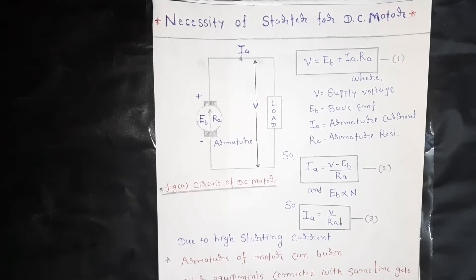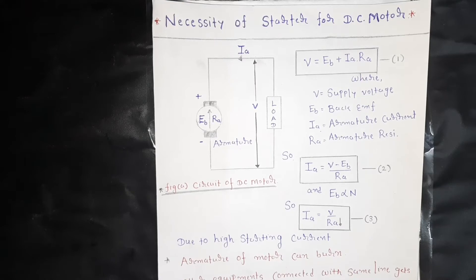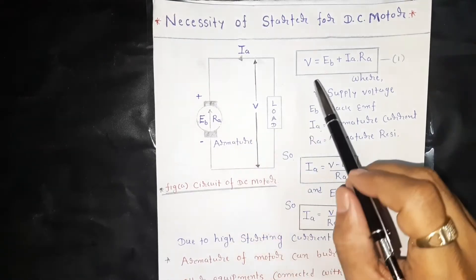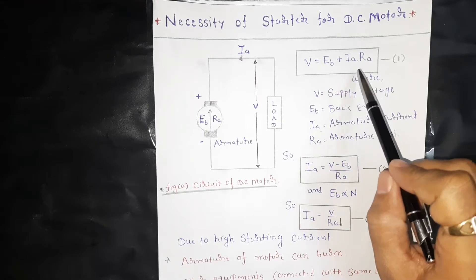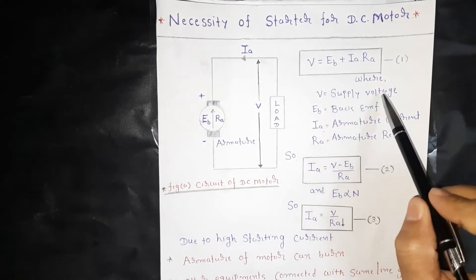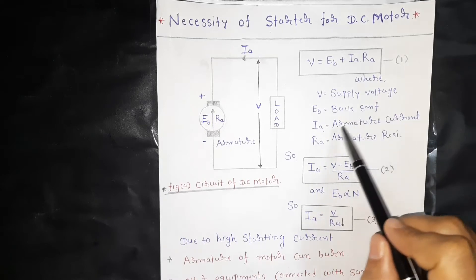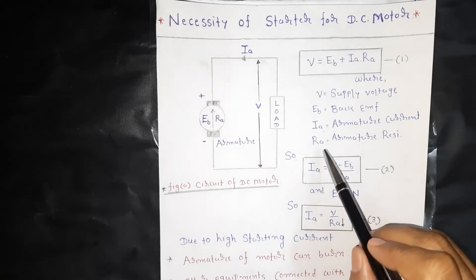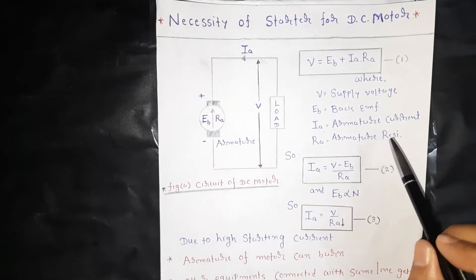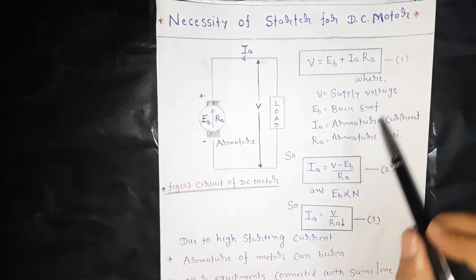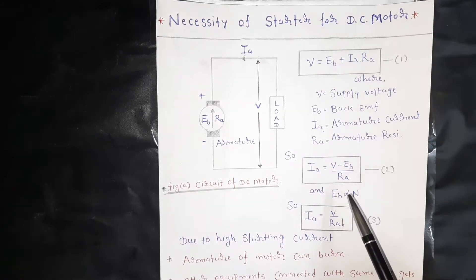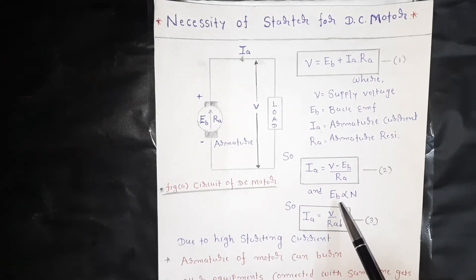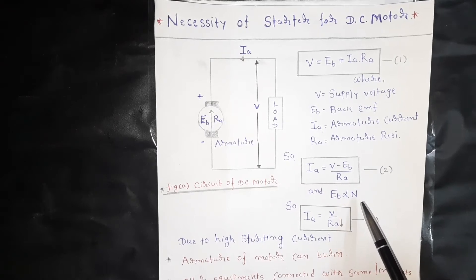First of all, let us discuss what is the necessity of a starter as far as the DC motor is concerned. This is the circuit of the DC motor. The equation of the DC motor is: voltage V equals EB plus IA times RA, where V is the supply voltage, EB is the back EMF, IA is the armature current, and RA is the armature resistance. From this equation, we can write armature current IA equals V minus EB divided by RA. In the DC motor, the back EMF is proportional to the motor speed N.